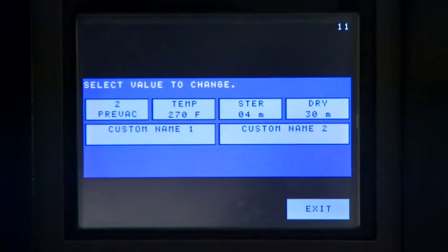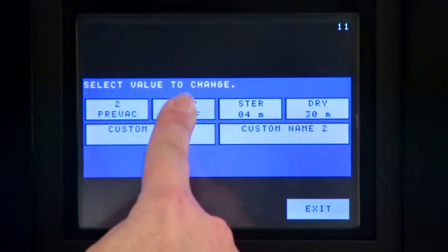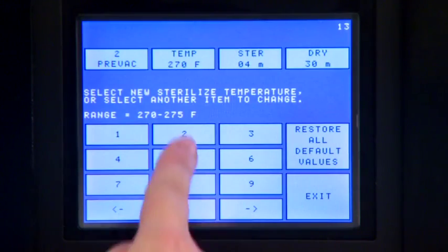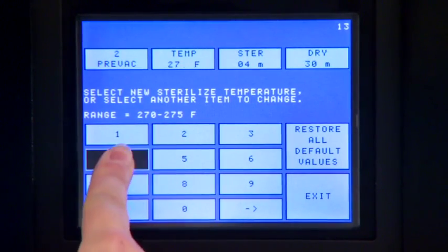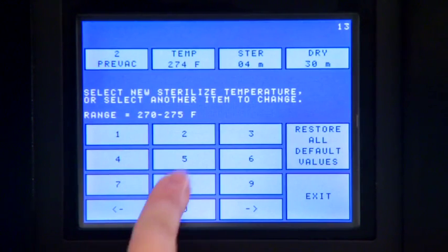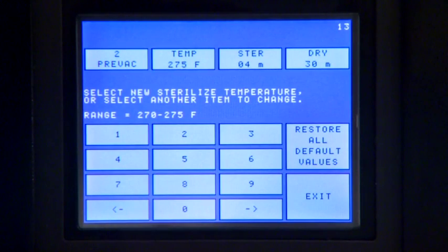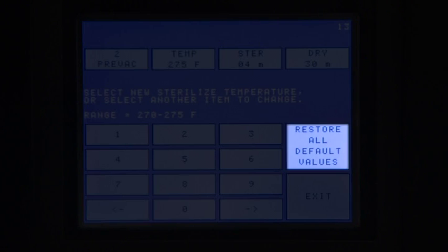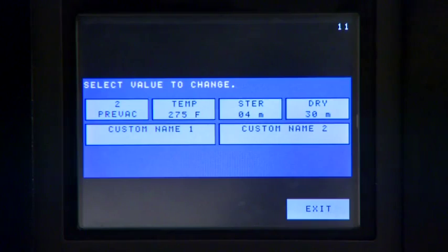For example, to change the sterilizer temperature value for a Prevac cycle, enter the desired temperature into the keypad, ranging from 270 to 275 degrees Fahrenheit. If you make a mistake, use the backspace button on the keypad to erase what you entered. Press the Exit button to accept the new value, or press the Restore All Default Values button to keep the factory set cycle value and return to the Change Cycle screen.